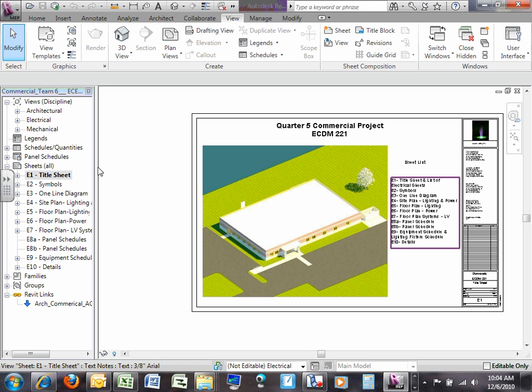So if you guys look at design criteria for power, what's the criteria? We sat with the owner and based on the function, based on our experience being the smart Alecs in town, we came up with this understanding of what a commercial building needs. So if you look at, for example, receiving room 120, they want 1 receptacle every 1,000 square feet. Is it wrong to put 2 receptacles? No. From this engineering firm's experience, 1 receptacle within 1,000 square feet, no code supports this.